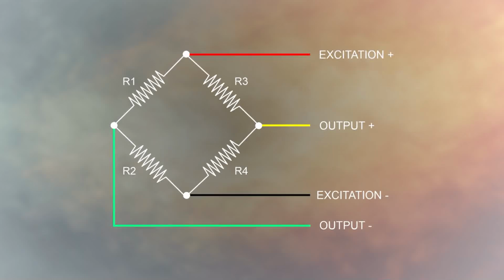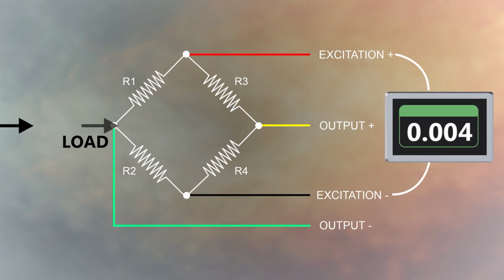It uses 4 strain gauges connected in a Wheatstone bridge. When no load is applied, the system is balanced, and the output is nearly zero. When a load is applied, the strain gauges slightly deform, changing their resistance. This unbalances the bridge, and generates a voltage proportional to the applied weight.